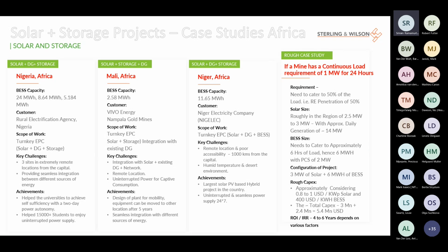So the configuration needed for catering to a 1 megawatt continuous load will be roughly around 2.5 to 3 megawatt of solar and approximately 5 to 6 megawatt hour of BESS.